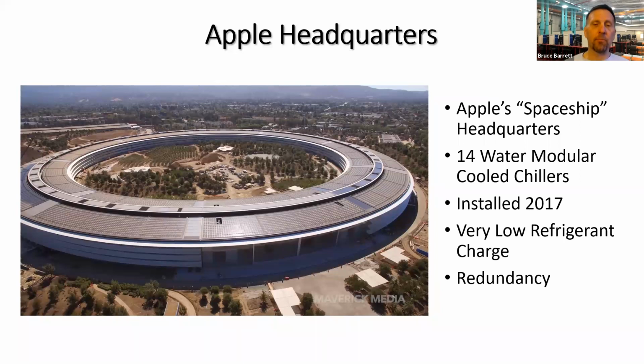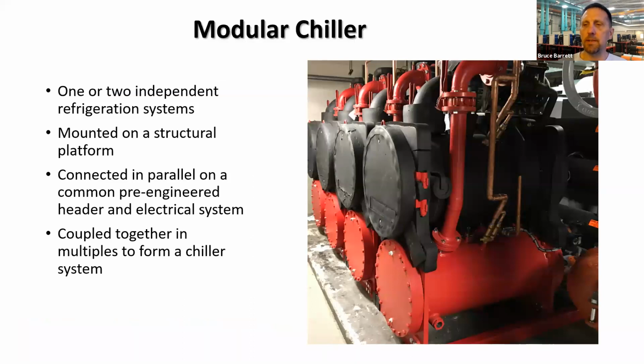To get some scale of this building, it's about 3/4 of a mile across. So it's a massive, massive building. So what is a modular chiller? It's multiple refrigeration circuits on the water side, piped in parallel. They can be mounted on a single structural platform. We can do that in our factory as well, pre-mount them. But typically, if you're going modular, you're trying to get it into a smaller place, through a 36-inch door, up to a penthouse, up an elevator shaft. All of these are controlled by a common master controller and typically linked together on the water side via grooved couplings. Very easy install.